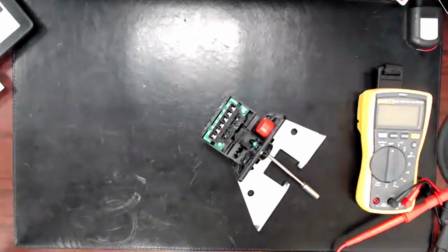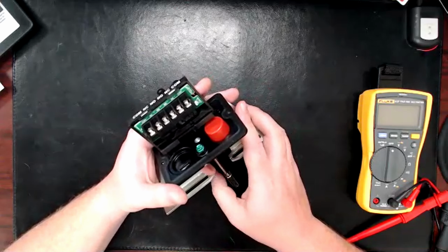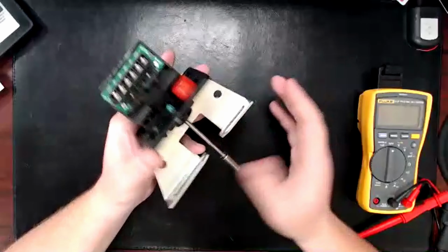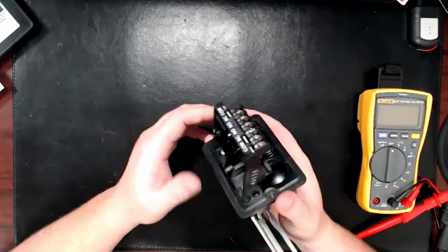And there are other times when you might actually have to mess with one yourself. I've had a couple of service calls where I've had to adjust the valve, or the switch rather, with the valve. So there's a couple things to point out. First of all, you have two sets of switches because you have common, normally closed, and normally open that are these three terminals on this side. And then a separate switch, you have normally open, normally closed, and common on this side. So if you're using this common, you need to use these two terminals. If you're using this common, you need to use those two terminals.